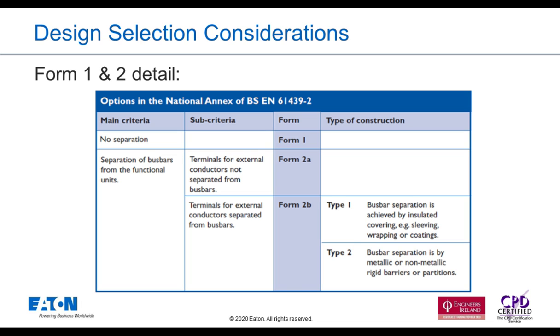So we'll look at each form in a bit more detail. So Form 1, I won't go into it. There's basically no separation between the 3 main components: your bus bar, your functional unit, and your outgoing cables. Form 2. So the main criteria for Form 2 is that the main bus bar is separated from the functional unit. So functional unit being your protective device.